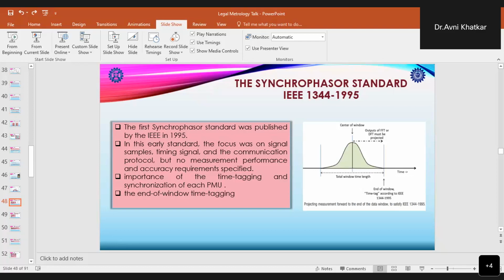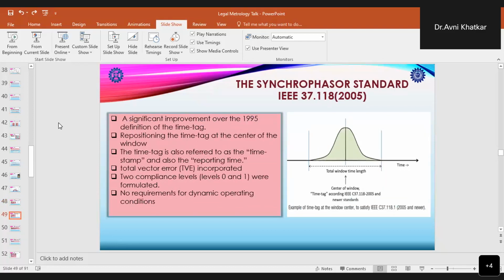So for improvement, this standard was revised, and a significant improvement was seen over the 1995 standard in the 2005 standard, basically on the basis of the redefinition of the time tag. Repositioning the time tag at the center of the window was done, which removes the need to project the measurement forward in time with all the uncertainty that brings. Window center time tag placement continues to be the most modern version of the standard.